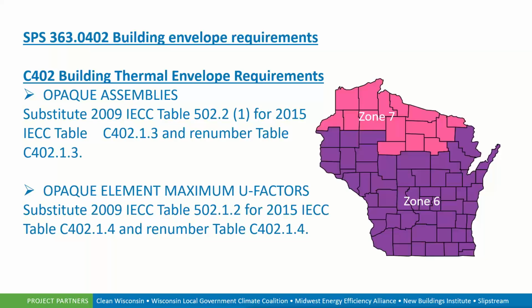So opaque assemblies. So if we have opaque elements, the U factors, the same thing. There's a new table that was substituted from the 2009 IECC in place of the published 2015 code. So just be very certain that you're looking at the appropriate fenestration tables. And this is just an example of those tables. We have the opaque assemblies where we have our R values, and we have our equivalent or maximum U factors. And these are those substituted tables from 2009.